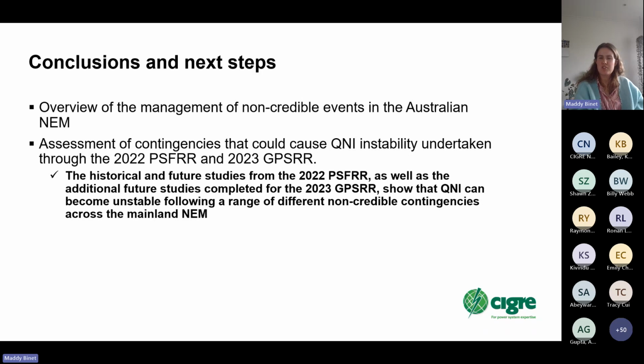In terms of machine learning models, at the moment we're not using anything like that. It's more looking at trend analysis and picking out the boundary conditions in terms of what we think is a worst case for the contingencies we're looking at, and that's how we pick which historical dispatch conditions we'll study. So obviously looking at the ones with the largest contingency size or the worst network flow cases, or if it's a system strength issue, picking the ones with least synchronous units online. So that's how we pick which conditions to study. I don't know if that answered the question.